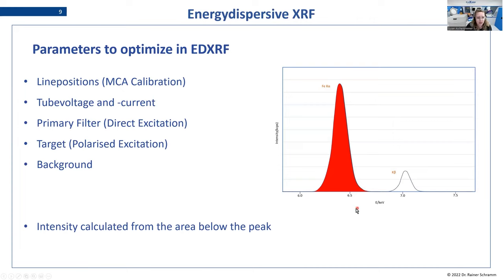We see the same thing for another sample with the same preparation and same application package — it's a feldspar. In this case, we have a lot of sodium in the sample. Again, the mean value is okay for the ED measurement, but the standard deviation is way higher than for the WD values. As we move further along the periodic system, the results become more comparable. For strontium, we see that we are even a little bit better in the ED than in the WD.